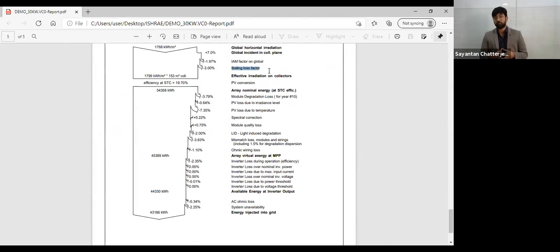Then comes the major part, PV loss due to temperature. This PV loss due to temperature comes from different locations, their ambient temperature, and also their mounting structures. If we are installing the solar power plant on a tin shed roof, there is very little space for air circulation, so the heat is generating and the temperature is increasing. In case of a flat roof, we get PV loss due to temperature in Kolkata nearly 7 to 8%, and if installed on a tin shed roof it drastically changes up to 12 to 13%.